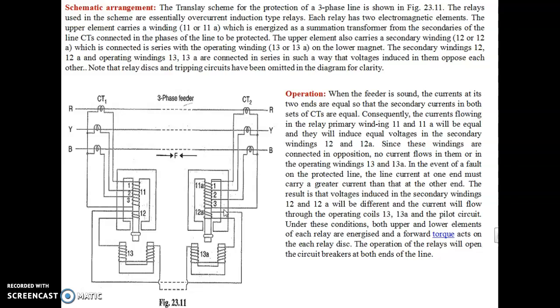The Translay scheme uses essentially overcurrent induction type relays. Here we are using induction disc type relays, right? See here, each relay has two electromagnet elements. The first one is the upper magnet and this is the lower magnet. Okay, the upper magnet is M shaped, the lower magnet is U shaped. See here, the upper magnet element carries the primary winding and secondary winding.